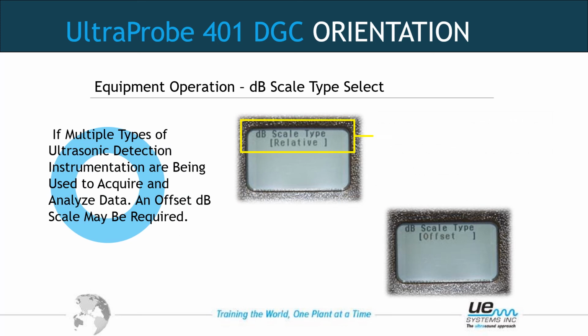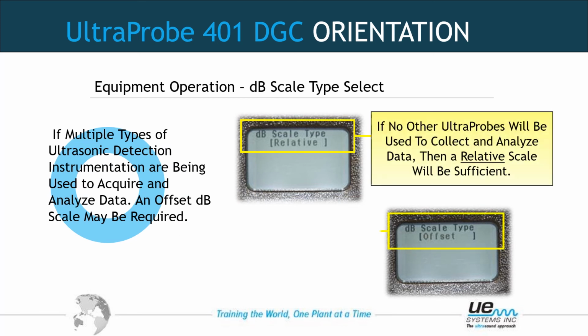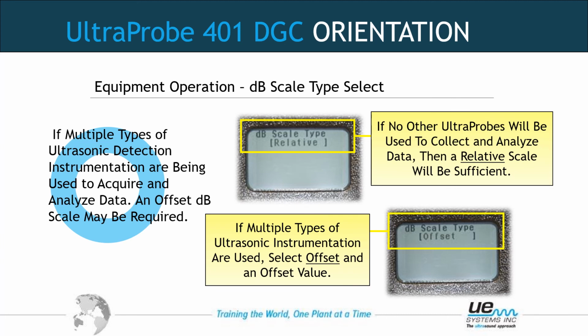The next menu item down is dB scale type select. This is fairly important. If we have 2 different units taking readings, for instance, if we were using an Ultraprobe 10,000 with a stethoscope module to take the readings and trend, but we use the 401 digital grease caddy with the magnet to come back and do the lubrication, and we're loading the same route to both units, those 2 units will read differently because one has a stethoscope module and one has a magnet. So the scale would not match between the 2 units because they're using different modules.